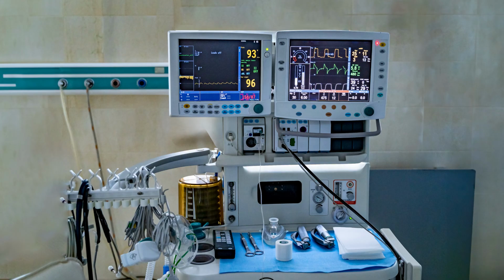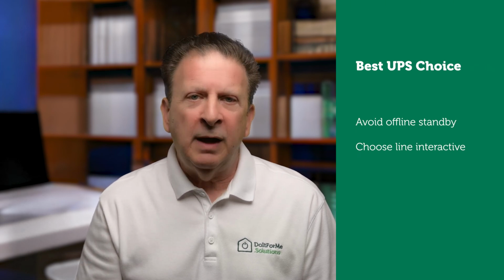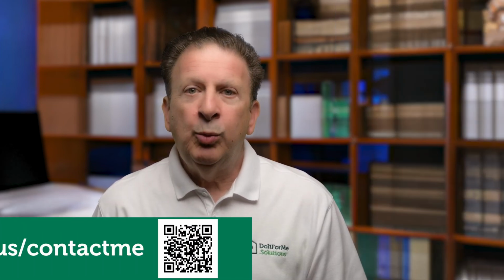As you might guess, the online double conversion UPS is the most complex and therefore most expensive kind of UPS system. It is best suited for life-sustaining or life-saving medical devices and complex precision industrial equipment and machines that must be absolutely protected from any kind of power fluctuation or power failure, and is beyond the budget for most typical home or consumer use. So the TLDR, avoid offline standby UPS systems and make sure anything you are considering has at least a line interactive design.